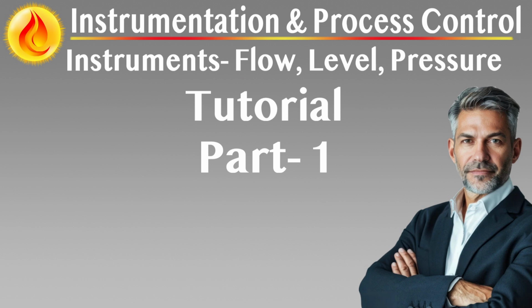Smart signal transmission and resilient power infrastructure for field instrumentation. Signal transmission architecture must reinforce both operational reliability and lifecycle adaptability. Where analog outputs are employed, intelligent communication over the 4 to 20 milliamps loop should be the default configuration, enabling bidirectional device communication for diagnostics, calibration, and configuration. HART protocol is the industry-preferred standard supported across most vendors and providing backward compatibility with legacy analog systems.